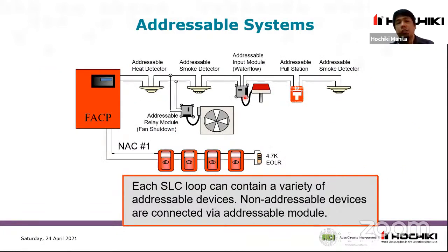Okay? So this is the common single line diagram. Each SLC loop can contain a variety of addressable devices. Non-addressable devices are connected via addressable module. So ito sa sample natin sa screen is addressable heat detector, addressable smoke, addressable input module, addressable pull station, and addressable smoke detector. So yung mga devices na i-connect natin like water flow and fan, yung pressurization fan, kino-connect natin via module. So yung module yung na-connect doon sa addressable loop natin since yung module yung addressable. So ito yung kinokontrol natin if magkakaroon ng activation.